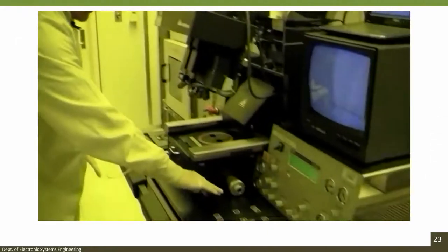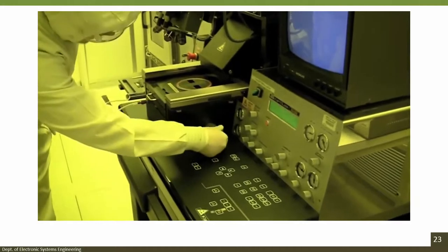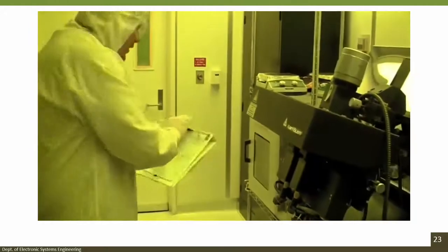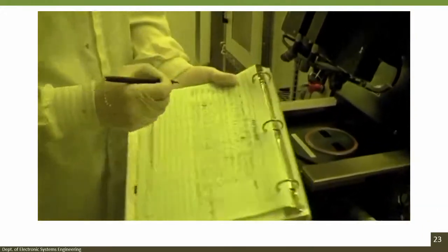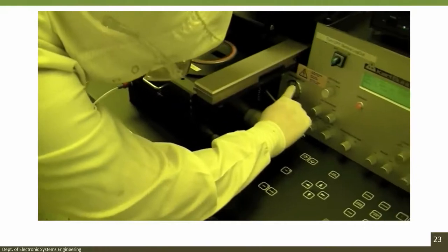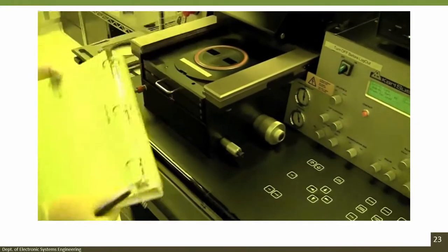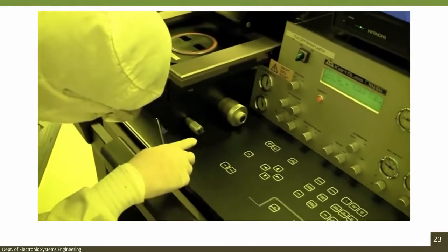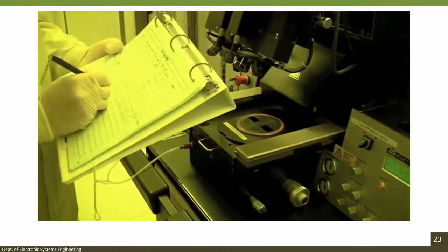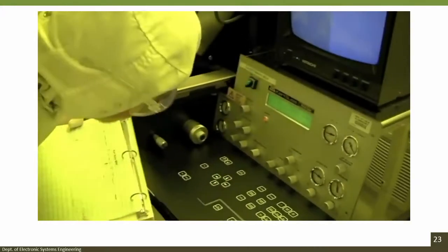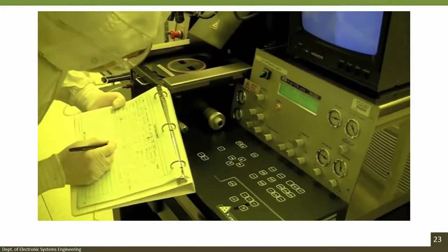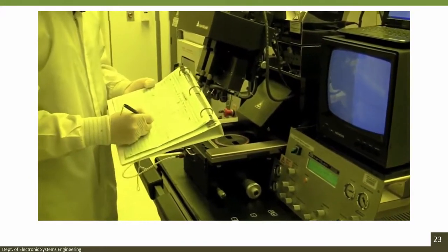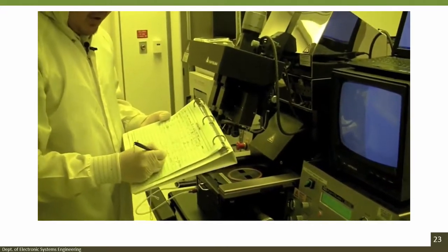So we want to make sure everything's in the standby position that you started the machine with. And then before you turn it off, you want to make sure you write in the logbook the different parameters. So the compressed air is about 4.9. The nitrogen is about 1.65. The vacuum is about -0.86. We used a 4-inch silicon wafer, and we did a 25-second exposure.